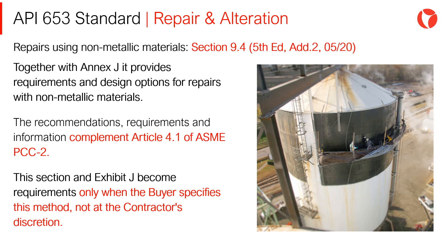Repairs using non-metallic materials, section 9.4: together with Annex J, it provides requirements and design options for repairs with non-metallic materials. The recommendations, requirements, and information complement Article 4.1 of ASME PCC-2. This section and Annex J become requirements only when the buyer specifies or allows this method to be used, not at the Contractor's discretion.